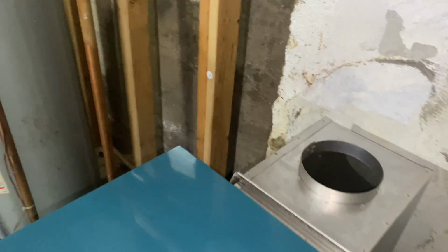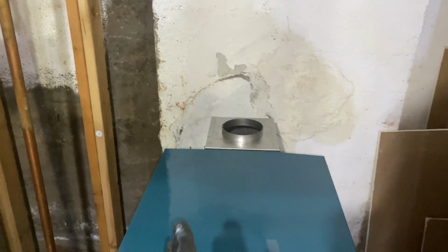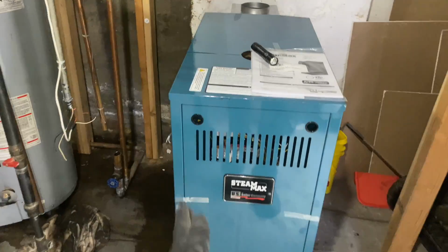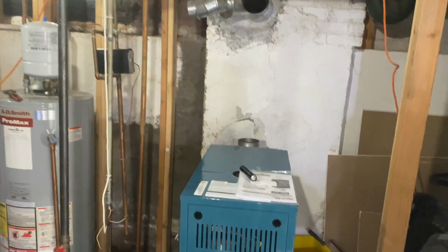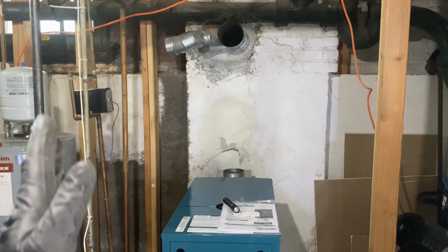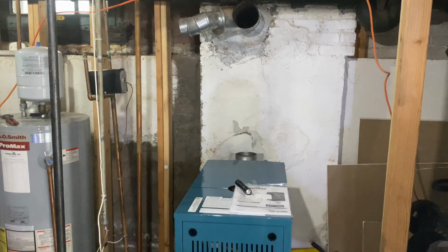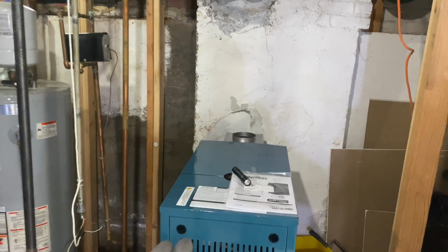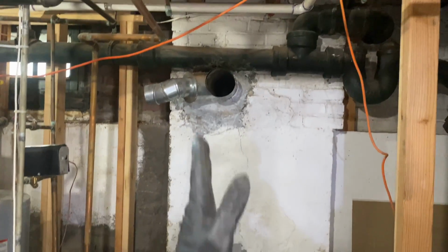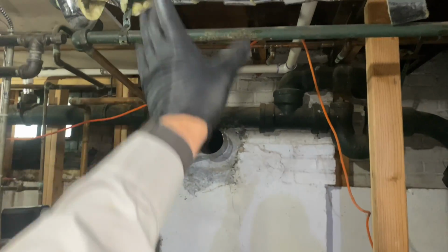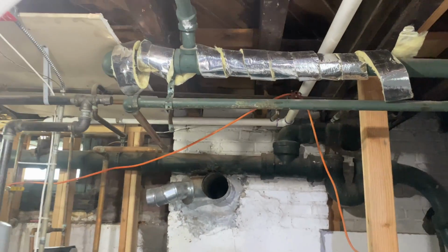But as I was saying, the reason we need a stainless steel chimney liner with gas-fired heating equipment is because of the exhaust temperature, or the stack temperature, which is considerably less than oil-fired equipment. With oil-fired equipment, you will find a terracotta or clay lining on the inside of the chimney that goes up to the top of the house.